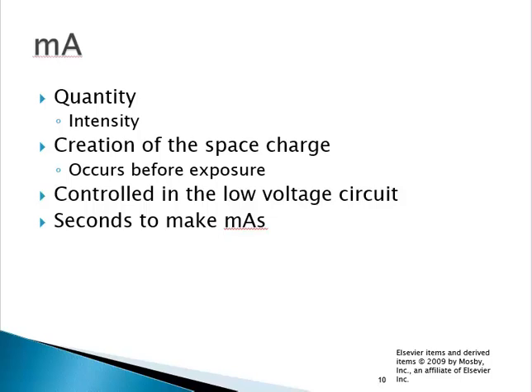MA is controlled in the low voltage circuit. When you set your MA, you're selecting different contacts on the low voltage circuit before the voltage is stepped down. We only use 25 volts to heat the filament because all we're doing is heating the filament. The distance between filament and anode is short, so if we used 110, 120, or 220 volts, we could get flow of electrons from cathode to anode with a large space charge — and we don't want that. We want to keep electrons on or around the filament, so we use 25 volts tops.